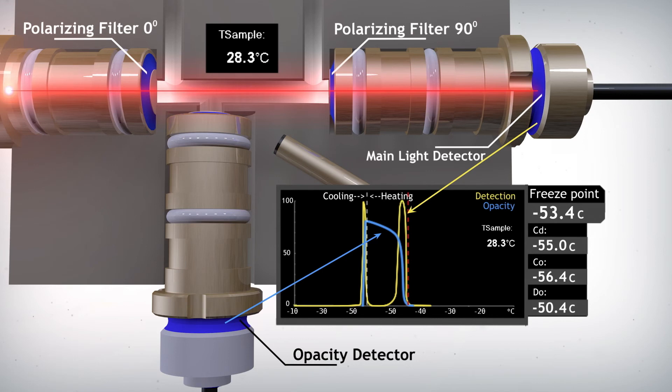Larger crystals are detected by the secondary, or opacity detector, and are usually at a slightly colder temperature, shown as CO for crystal opacity. The last of the larger crystals that melts is shown as DO. The temperature at which the last fine crystal melts determines the freezing point. The temperature difference between DO and freezing point is usually small.